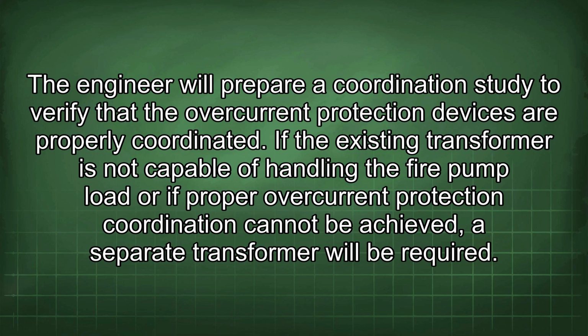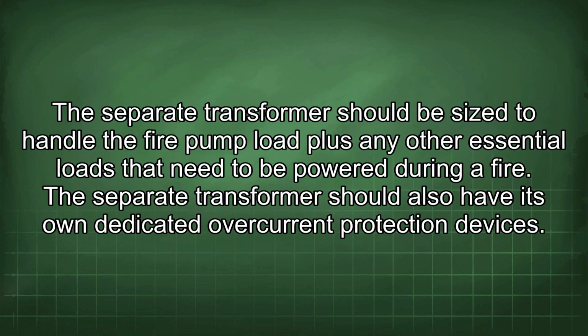If the existing transformer is not capable of handling the fire pump load or if proper overcurrent protection coordination cannot be achieved, a separate transformer will be required. The separate transformer should be sized to handle the fire pump load plus any other essential loads that need to be powered during a fire. The separate transformer should also have its own dedicated overcurrent protection devices.